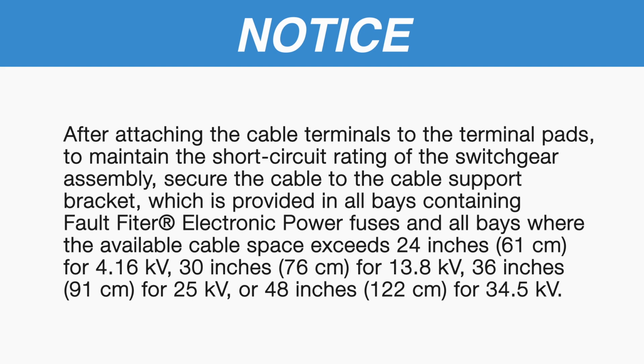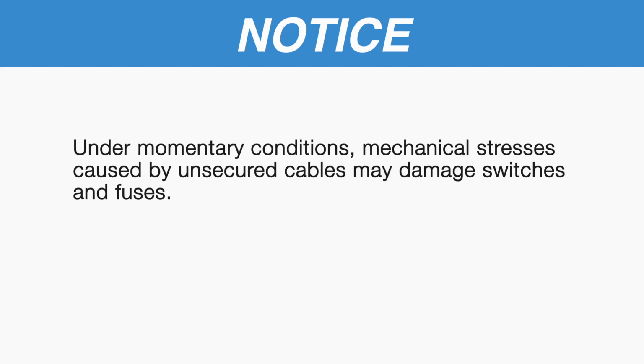After attaching the cable terminals to the terminal pads, to maintain the short circuit rating of the switchgear assembly, secure the cable to the cable support bracket, which is provided in all bays containing fault fighter electronic power fuses and all bays where the available cable space exceeds 24 inches, 61 centimeters for 4.16 kilovolt, 30 inches, 76 centimeters for 13.8 kilovolts, 36 inches, 91 centimeters for 25 kilovolts, or 48 inches, 122 centimeters for 34.5 kilovolts. Under momentary conditions, mechanical stresses caused by unsecured cables may damage switches and fuses.